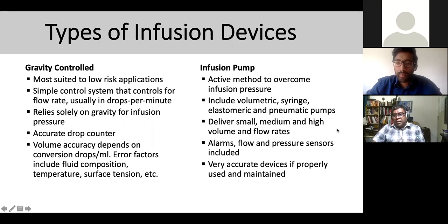So with infusion pump, you're talking about active mode with the pressure occlusion, all this controlling by rate flow, delivering small quantity of flow, and you can deliver high flow as well. So they've got alarm sensor, pressure sensor to monitor the flow. That's on infusion. Gravity is most of the time what you're going to see. So, the old way of doing it.